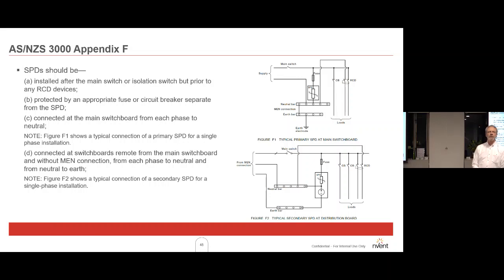Anyway, SPDs should be installed after the main switch or isolation switch, but prior to any RCD devices. They should be protected by an appropriate fuse or circuit breaker, separate from the surge protection device, and they should be connected at the main switchboard from each phase to neutral.